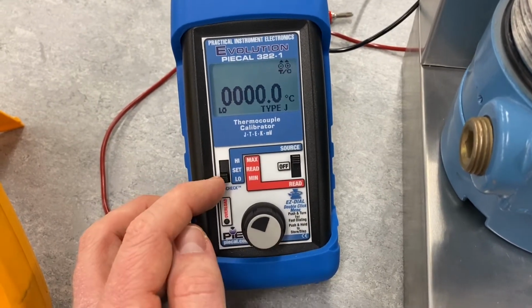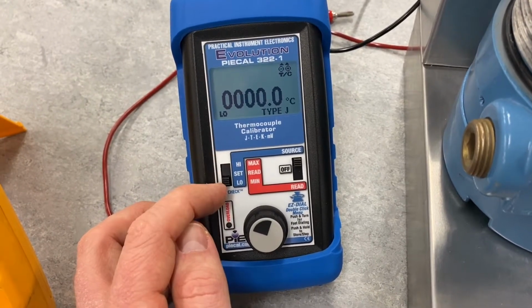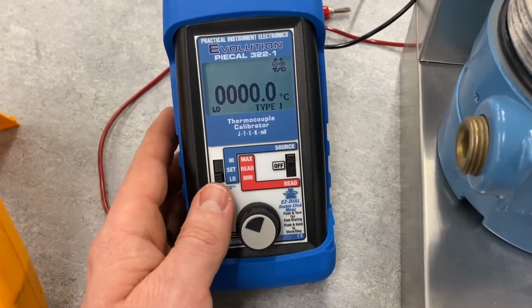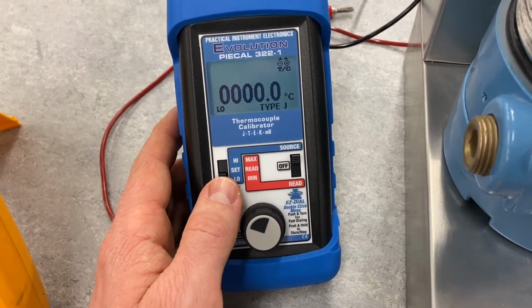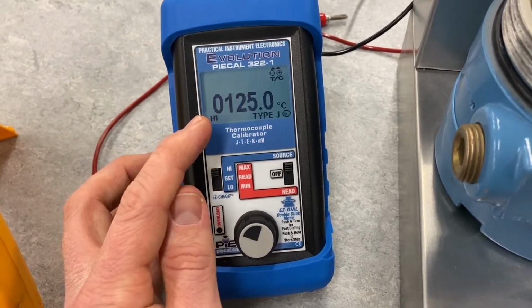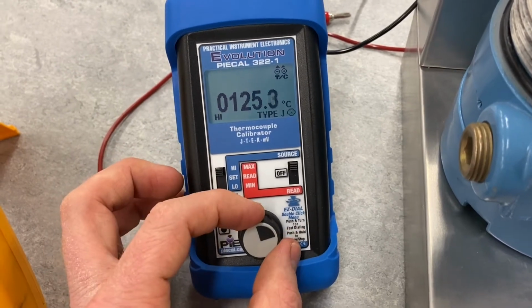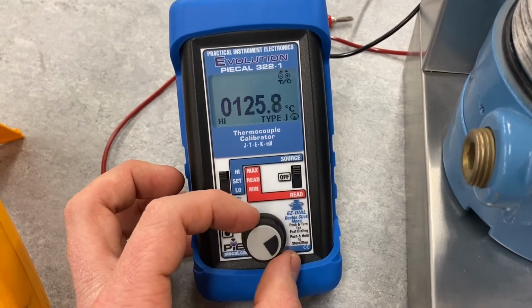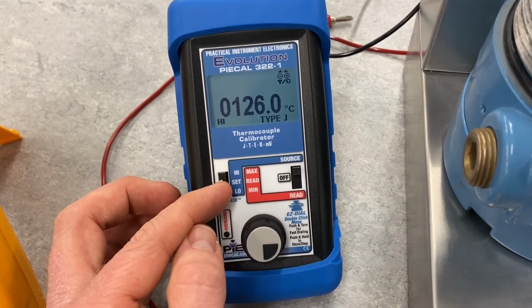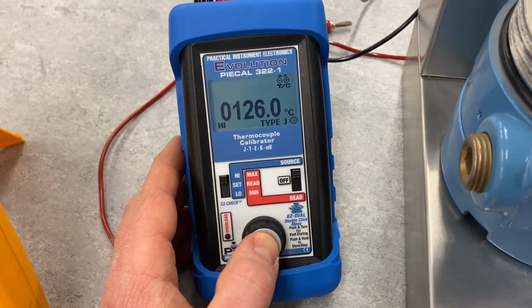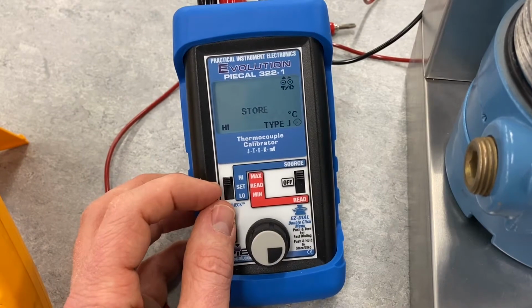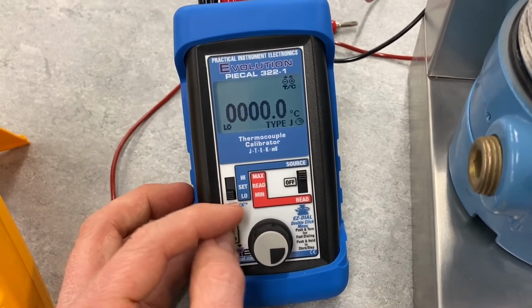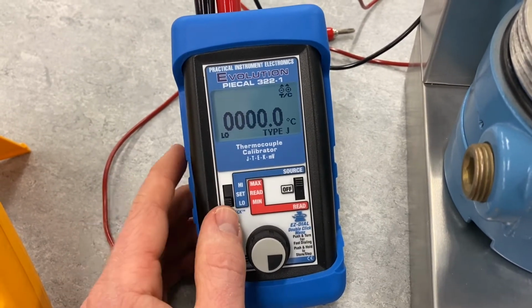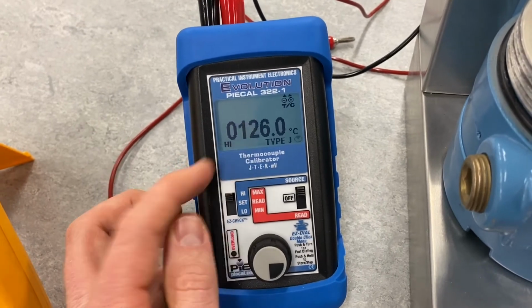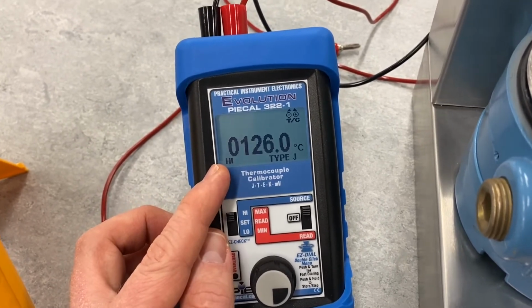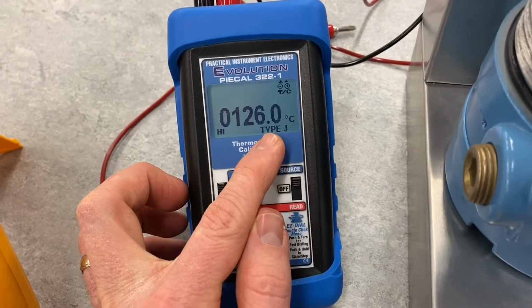Nice feature here is it has a low and a high setting for when we're doing a calibration. So to do the high setting, we'll go up, you can see it automatically goes to 125 as well. So if we wanted to change this to say 126, we could change it. As long as we have this switch up to the high setting, we press this button here, it will store that value. So now you can see if I go down to the low, it's at 0, we've set it for 0, and I can go back up, and now it's storing, it's outputting a value of 126 degrees C. So we need to be set for type J.